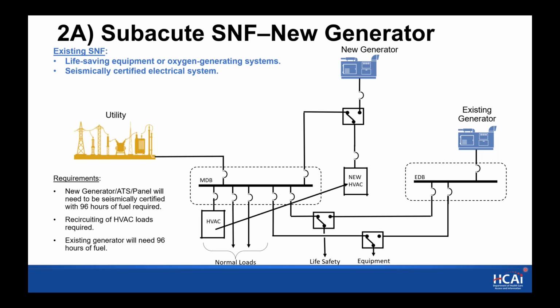now we're looking at the same scenario, but an existing subacute SNF, in which case it's assumed that there is life-saving equipment and or oxygen generating systems at the facility. So if those are currently already circuited to the equipment branch, you would have them backed up by a generator. If you put in your new generator, your new transfer switch, and transfer the cooling, the HVAC loads to the new system, you would now have a condition where your new generator backs up cooling for 96 hours, and that would need to be specially seismic certified, and it would need to have 96 hours of fuel. Your existing generator would be backing up the life-saving equipment and oxygen generating systems, and that would be required to have 96 hours of fuel for backup power.